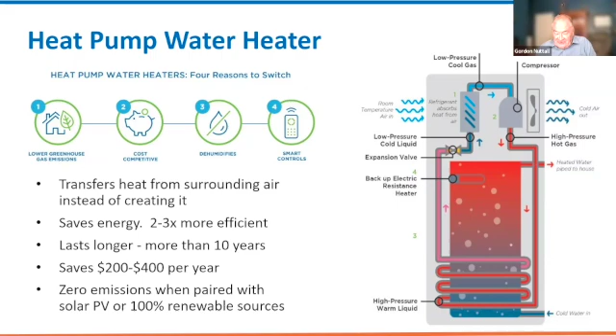One thing to consider with your heat pump water heater is where to locate it. It probably needs about 1,000 cubic feet of airspace, in your garage, utility room, furnace room, or storage room. Many people have their current water heaters in a small closet, and they can be vented or use a louvered door to reduce the amount of space that it requires. I believe that most of the 110 volt units are sufficient, and you may not need the backup heating element, which is really more suitable for homes that have, I don't know, 4 or 5 kids going to school in the morning, all of them wanting to get a shower before they catch the bus. A heat pump water heater meeting that kind of demand would maybe need that backup heating element.